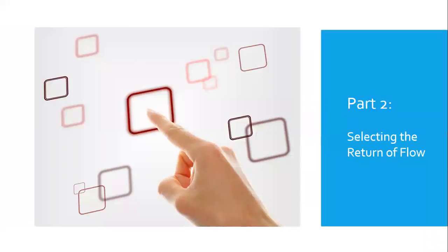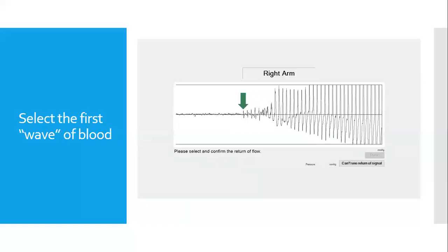Part 2, selecting the return of flow. After you've informed the PADnet software there is a strong pulse from the PPG probe, you're able to start the pressure test. The cuff will inflate and then slowly deflate before presenting you with a return of flow trace.